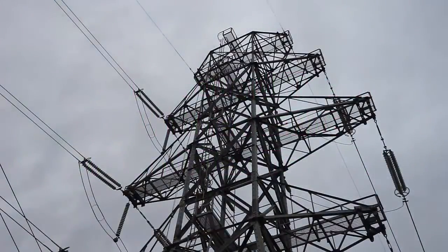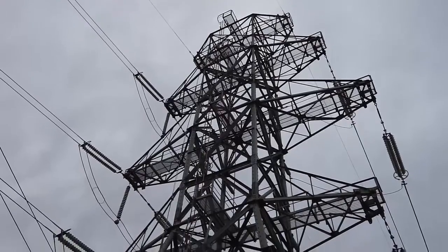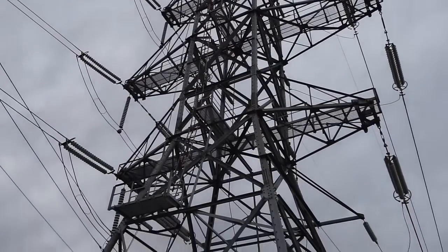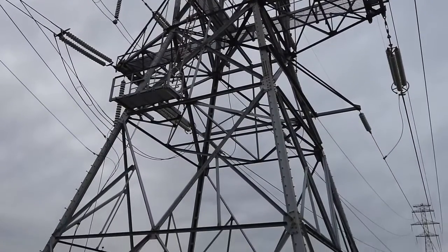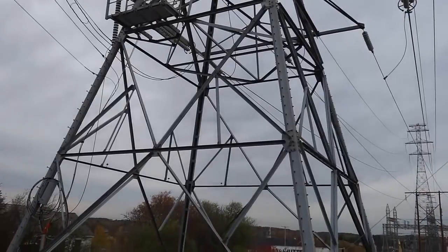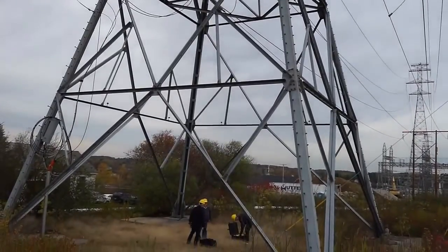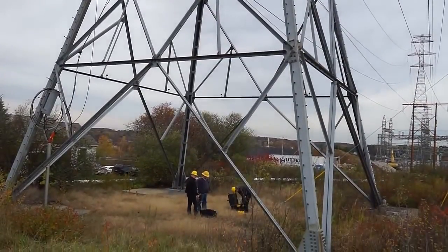Proper grounding is critical to power line transmission towers. These towers are highly susceptible to lightning strikes, which can result in dangerous flashover conditions. To ensure your transmission lines are adequately protected from this risk, it's essential to be able to accurately measure how well each tower is grounded, as well as test the quality of the overhead ground conductor connection.